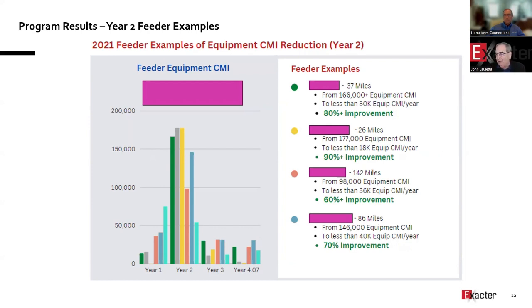Here's some more feeders, same type of analysis. But the key thing here is that the circuits were underperforming, but they weren't burning down. They were having flashover problems, which caused outages. They were having small issues that added up to many hundreds of thousands of customer minutes of interruption.